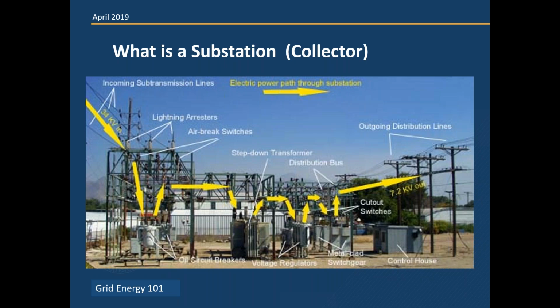So here's an example of a substation, and it's a collection of various equipment starting on the left side of the screen. It comes in on a 34.5 kV line, and it goes down through a couple of disconnects and some other devices, and it ends up in a circuit breaker. That's right, it's just a larger version of the circuit breaker you'll find in your panel at your house. And it steps over into the middle of the page, a step-down transformer, which steps it down to, I believe, a 7.2 kV distribution line, and it goes through a voltage regulator, and then another 12 kV or 7 kV circuit breaker, and then it steps out on the distribution system on the right.